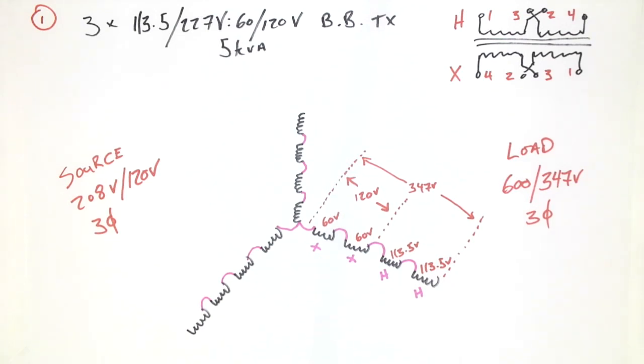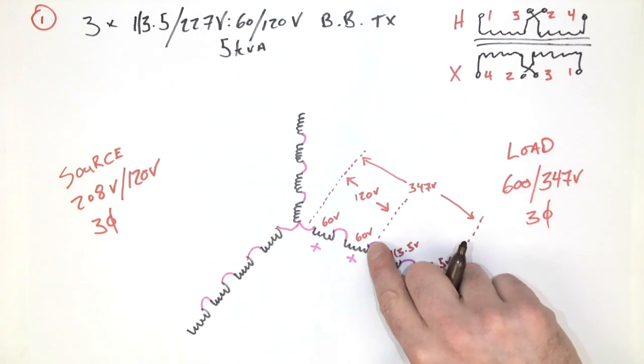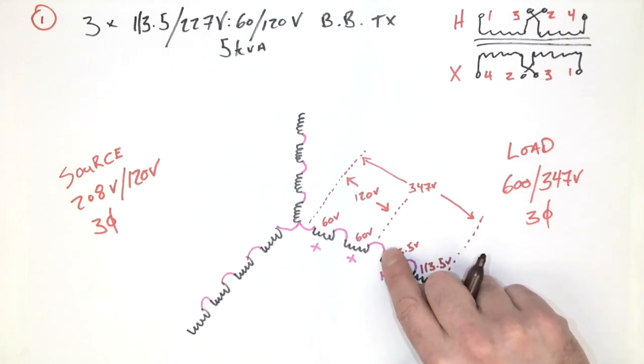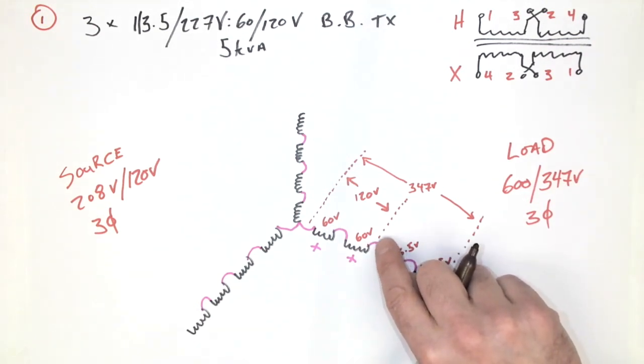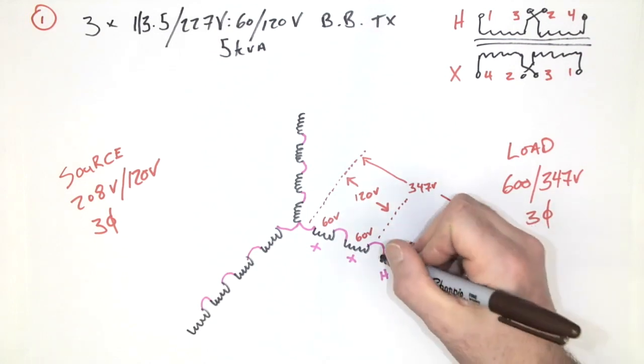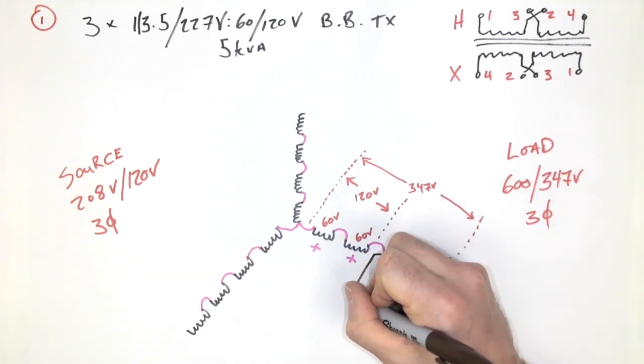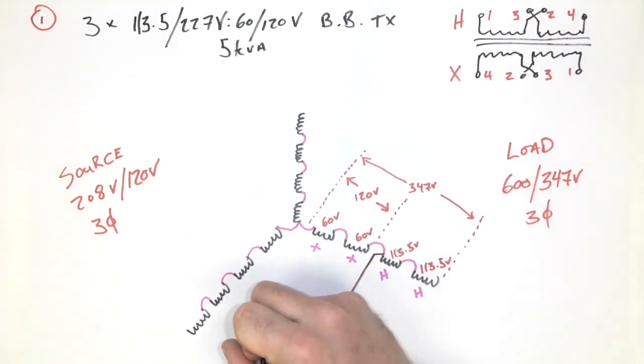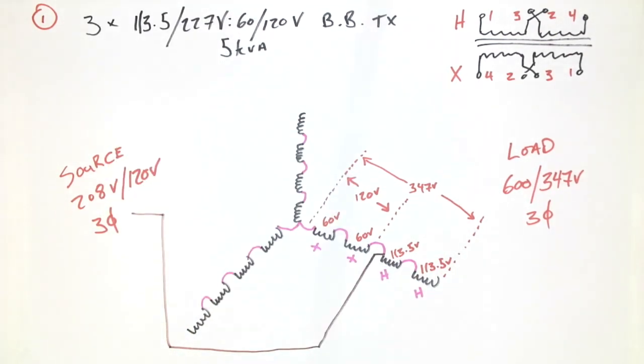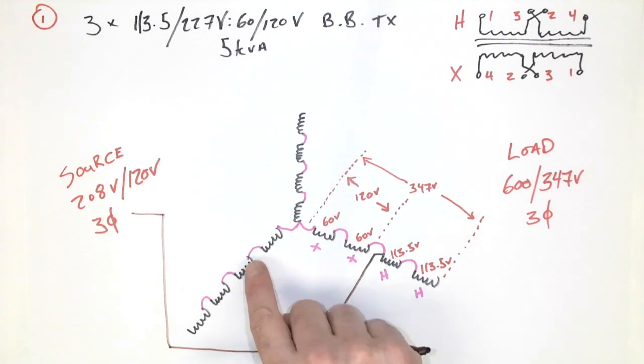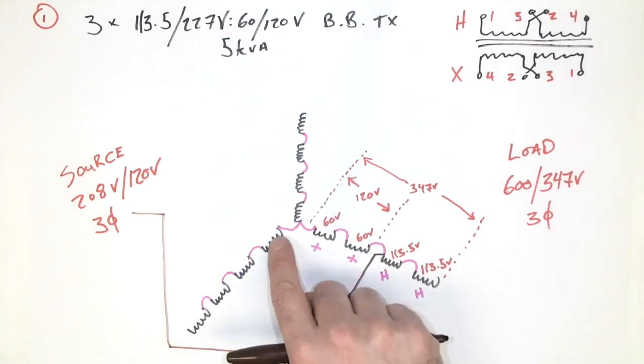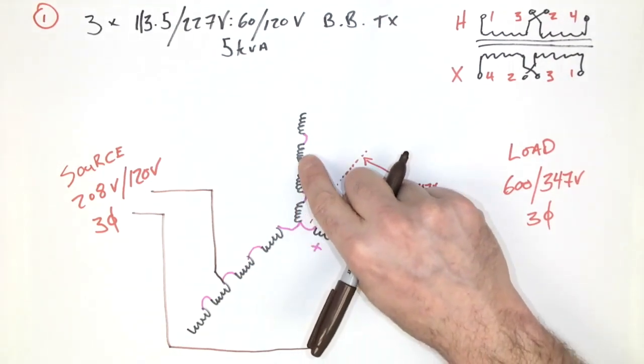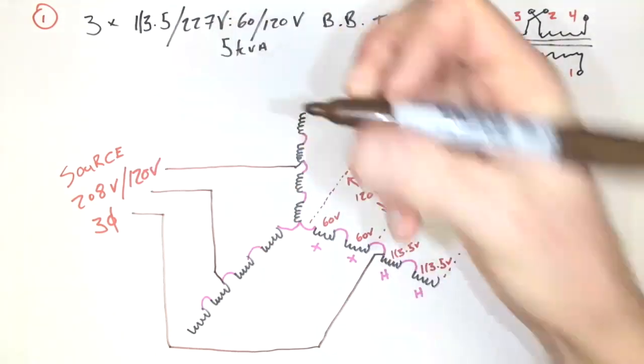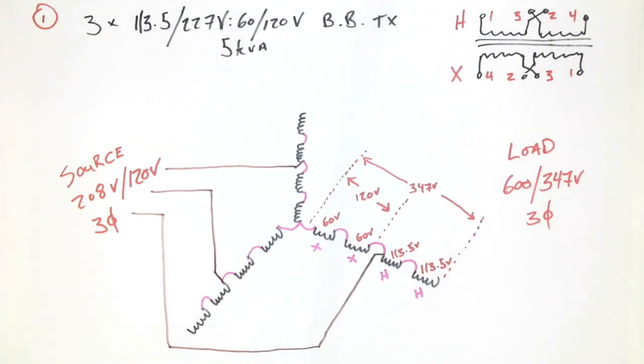I'm just going to sketch in where the load connection would go and where the source connection would go. The source connection is the lower voltage, and really the source connection could come from either this terminal here or this terminal here. It does not make any difference, and often you'll see a line just coming from the right from the middle of the jumper. I'm just going to choose to go from here, and we're going to have to go all the way over to the source. Now we're going to do the exact same connection for each of the other transformers. So those are the 2X, there's the H winding. And finally here, there are the 2X windings, there's the H winding. Great. So now we've got the primary or supply connection completed.